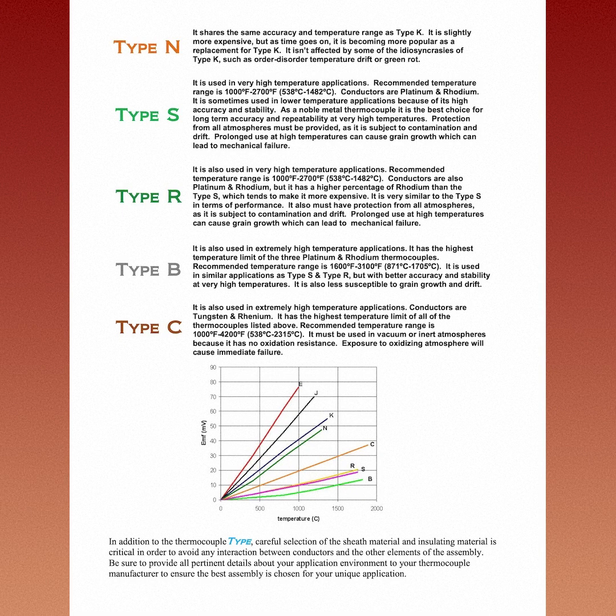In addition to the thermocouple type, careful selection of the sheath material and insulating material is critical in order to avoid any interaction between conductors and the other elements of the assembly. Be sure to provide all pertinent details about your application environment to your thermocouple manufacturer to ensure the best assembly is chosen for your unique application.